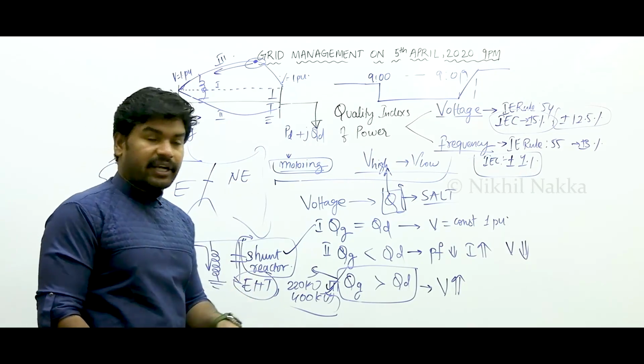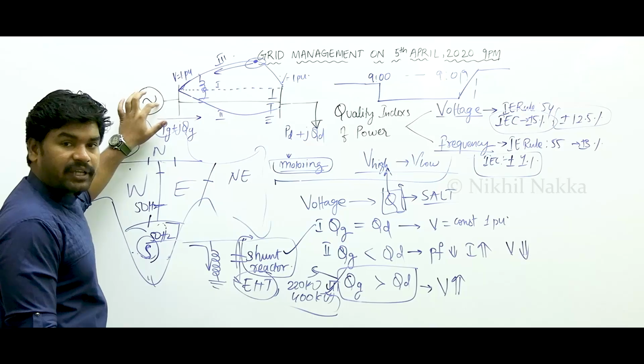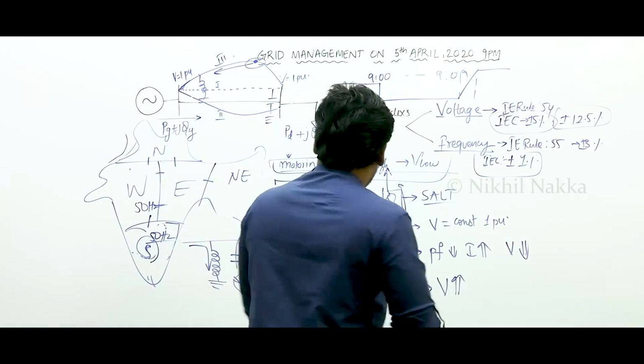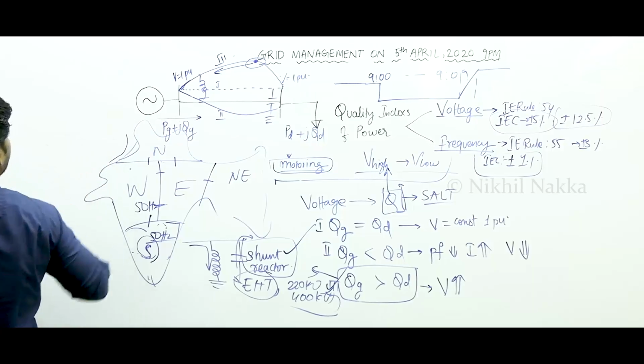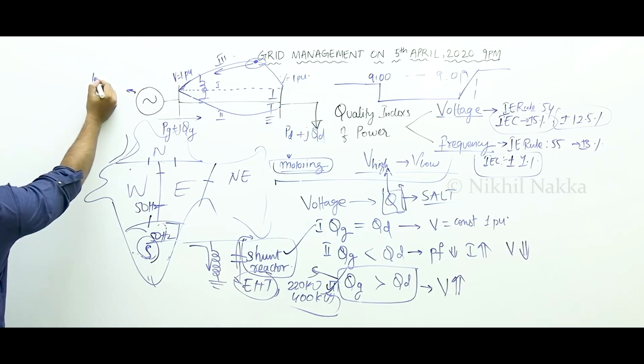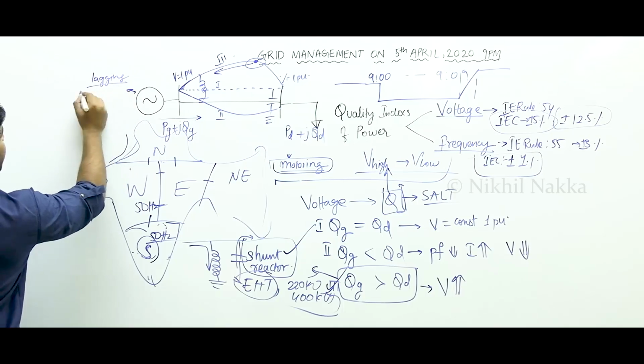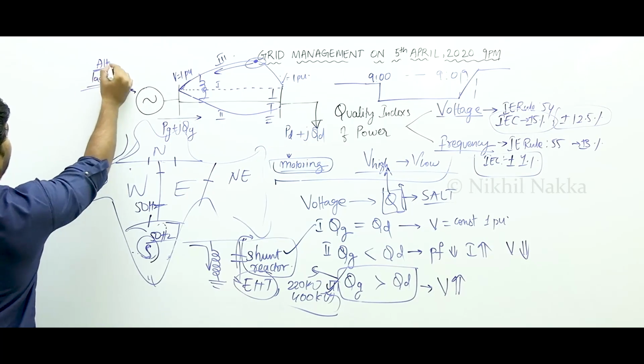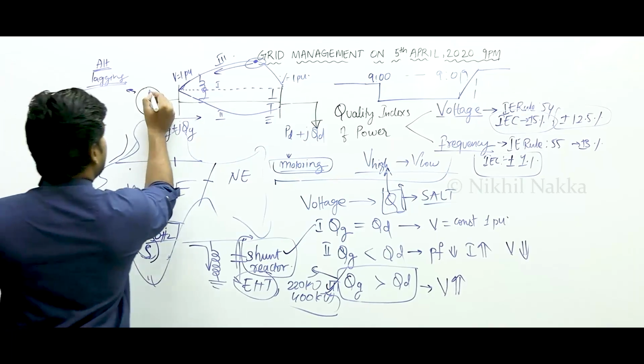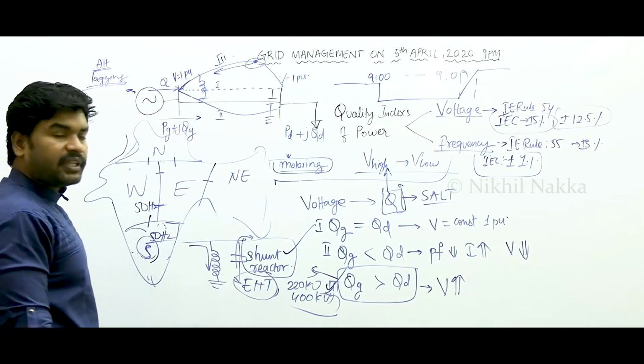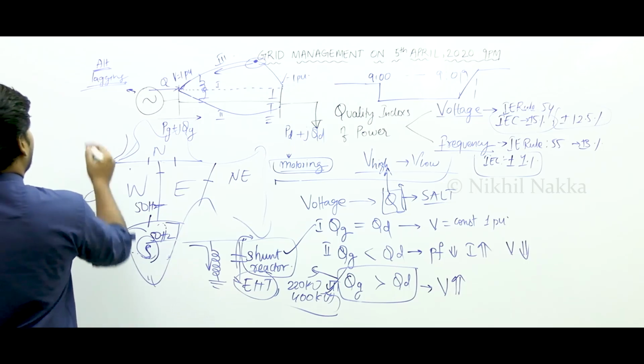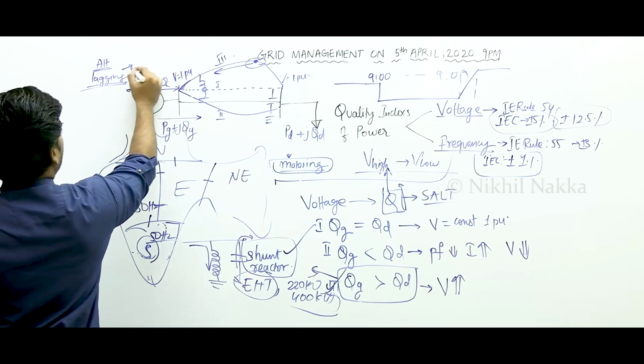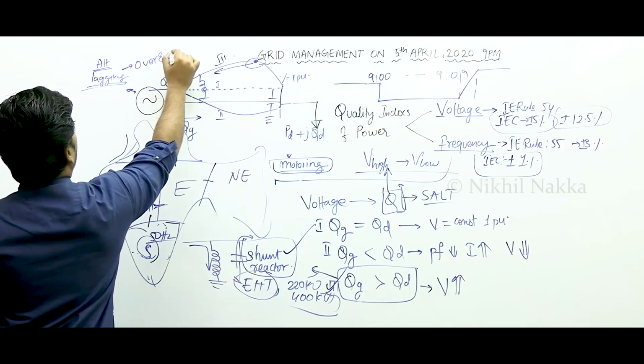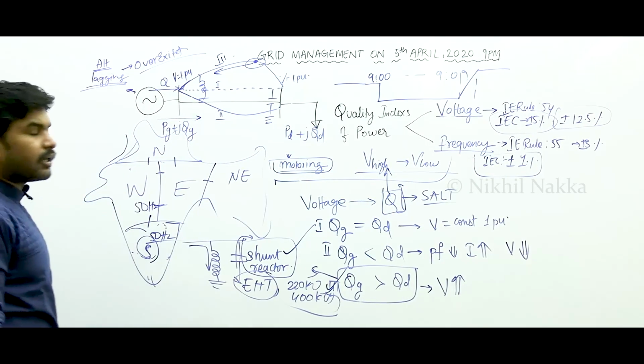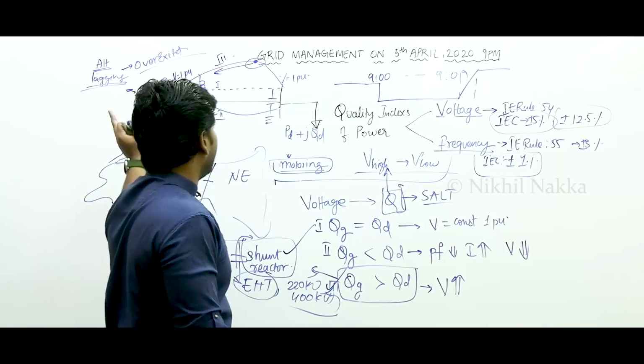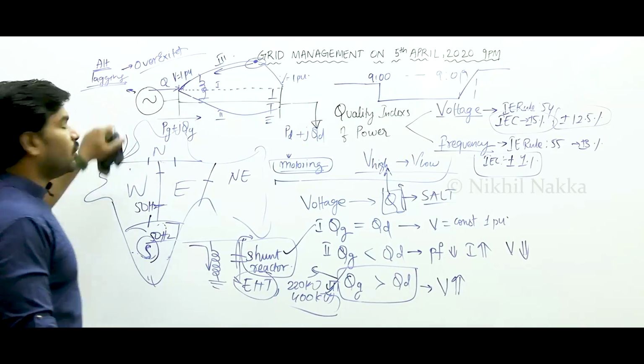And who else can absorb the reactive power? Generator also can absorb the reactive power. Is it, sir? How is it possible? See, a synchronous generator in a power station will be operating at which power factor generally? Lagging power factor. What do you mean by lagging power factor of an alternator? When the alternator is operating at lagging power factor, that means this fellow is delivering what? Reactive power. And this happens at which condition? Overexcited condition. When you are overexciting the synchronous generator, it will start generating the reactive power and it will pump it out. And the power factor would be lagging.